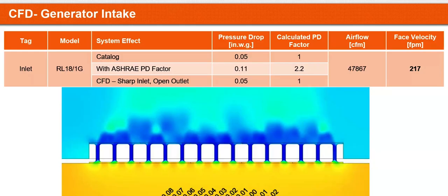So these silencers, at the very least, range from 3 to 5 feet. It's going to impede the transfer of that wave more effectively. But for that, you also have to close the air gap a lot. And if you're going to close the air gap to the degree that you have a low pressure drop, then your opening needs to be very big. So for that to be an ideal condition, so that your pressure drop doesn't double, that's where I try to give you the guideline of not exceeding that 300 feet per minute face velocity into the silencer or the louver. If you do that, you rest assured that you're not going to run into troubles with pressure drop.